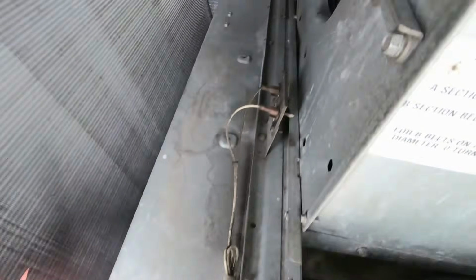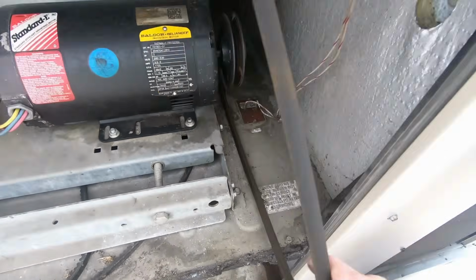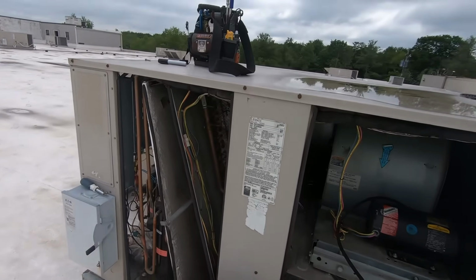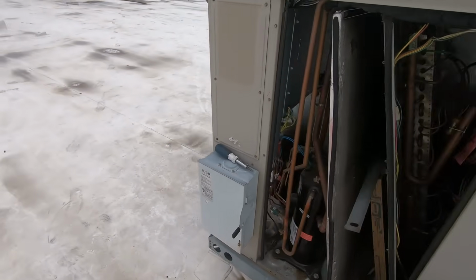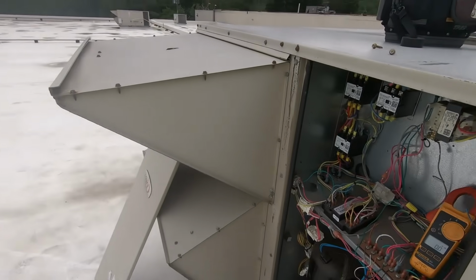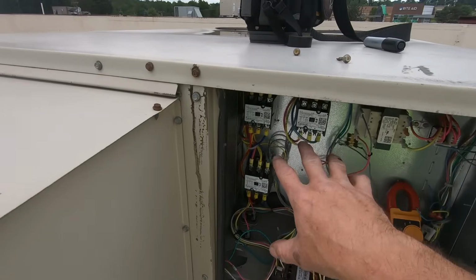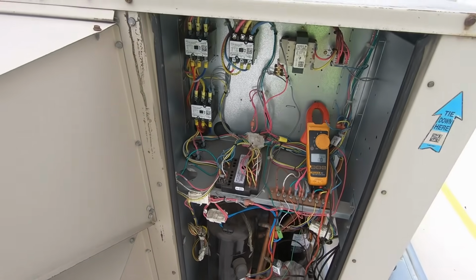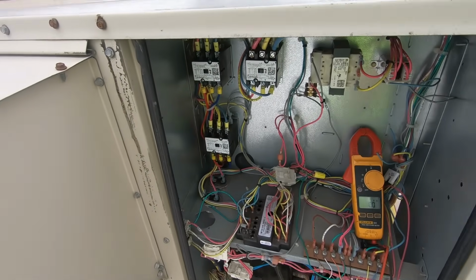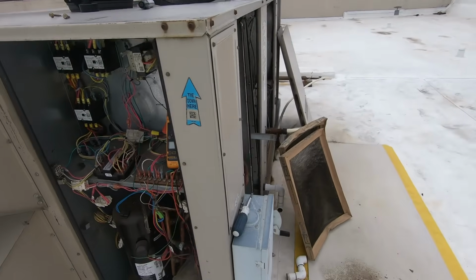Making a little bit of noise. I don't want to kill them on this first initial inspection, but we'll see how it sounds once we get it up and running. But I got to get pictures, check this heat exchanger, and I got to pull the covers off the contactors. I didn't get anything shorted to ground from right here at the contactors. I'm going to give it a more thorough look here in a minute and then go find a breaker.